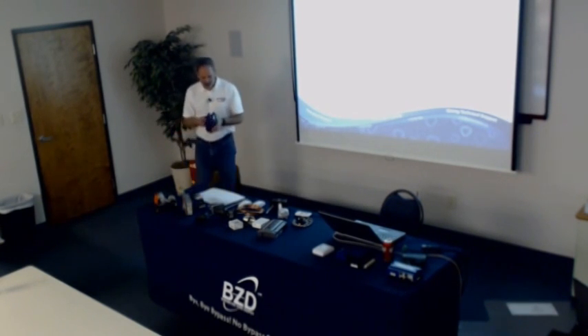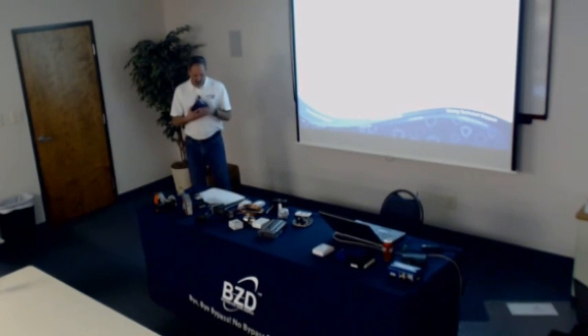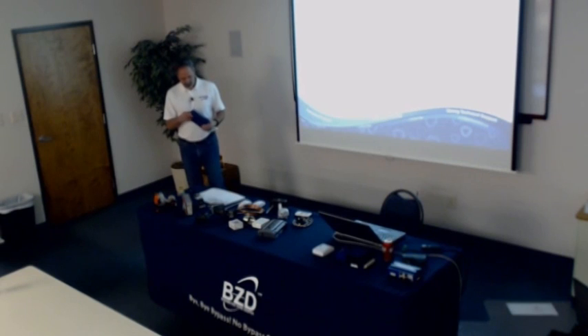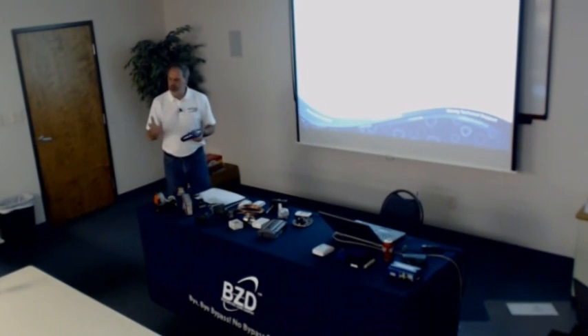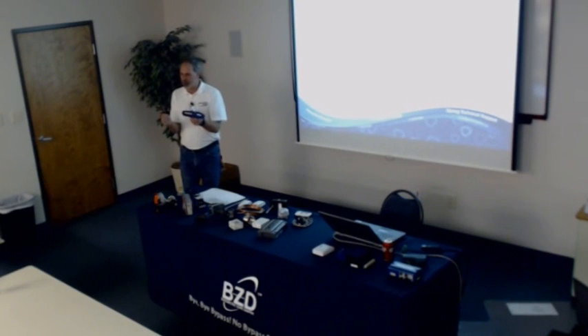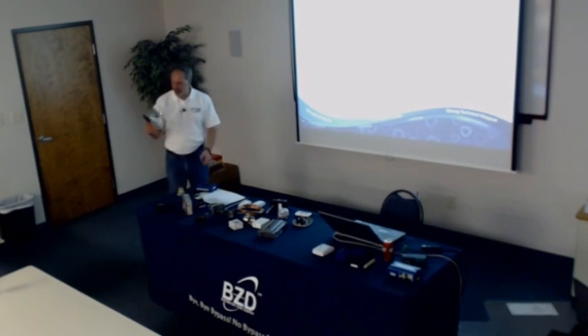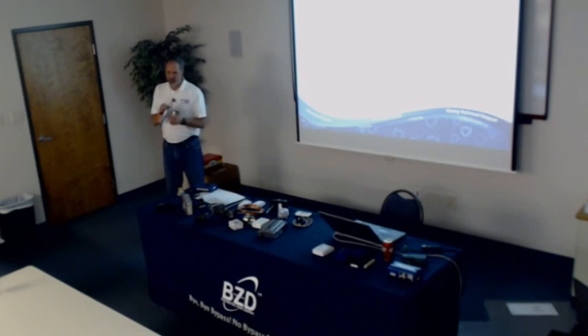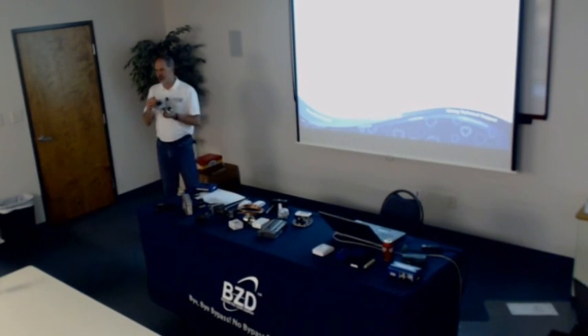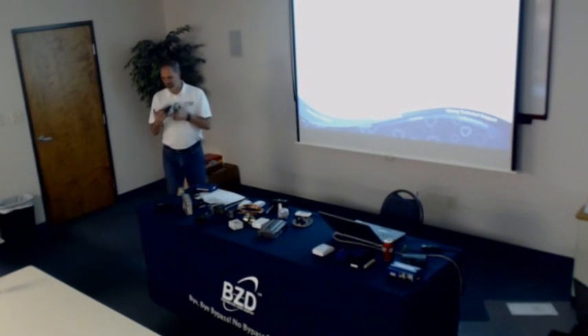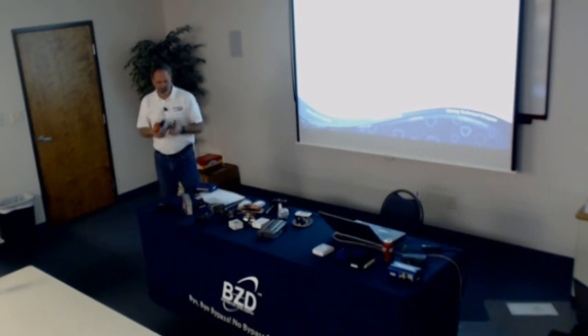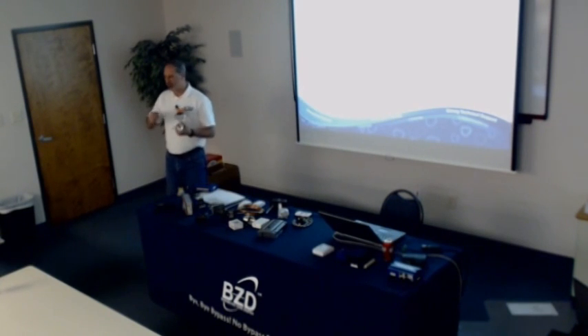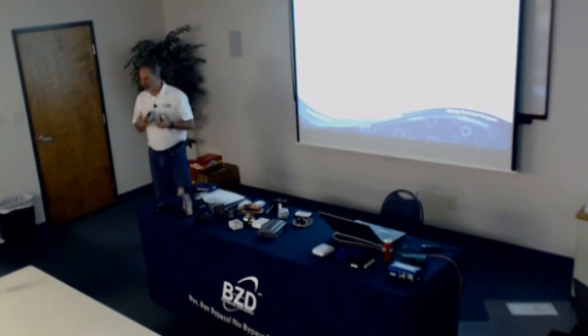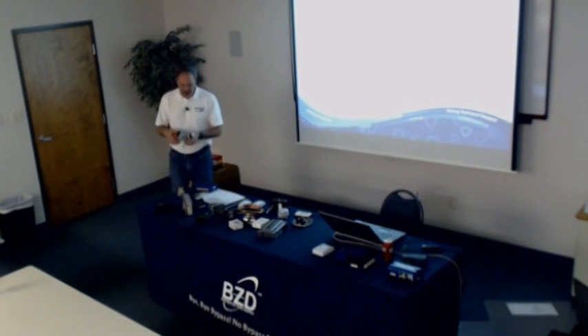So here at Jackson Systems, we're not a real big fan of anything that's 4 to 20. There's nothing wrong with it, and it has some advantages. But 0 to 10, it's nice to be able to just walk up and put your meter on it. If I want to check to see if this valve's working, and this guy happens to be 2 to 10, so at 2 volts it's closed, at 10 volts it's open, at somewhere around 6 volts it's half open, and you just put your meter on there and measure it. That's all there is to it. But if you do 4 to 20, you have to take one wire off, you have to move your leads, you have to get into the middle of the circuit, and the circuit doesn't work until your meter's hooked back up. So unless there's a special reason, we just do 0 to 10. It's just so much easier.